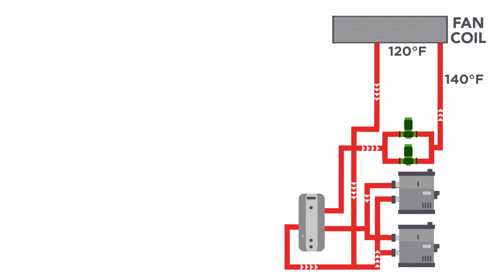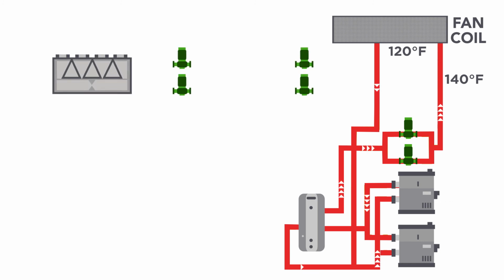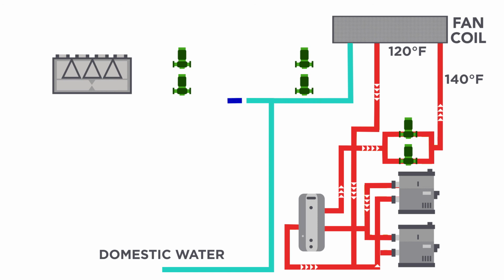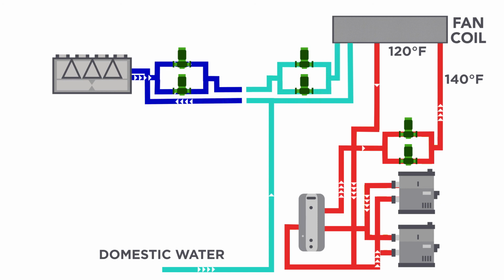To provide the cooling, we slightly modify the domestic cold water piping in the building so it can be used for both domestic and cooling in the building. A return pipe is added to the domestic cold water to make it a continuous circulating system, just like the hot water. We then add a chiller to the loop and isolate it by a double-wall stainless steel heat exchanger so it can be used to maintain our domestic loop at design temperature.